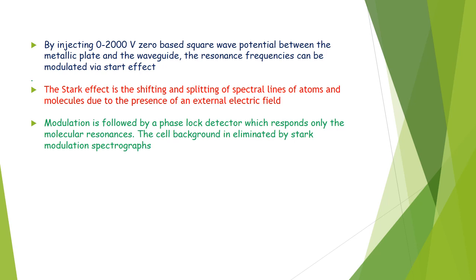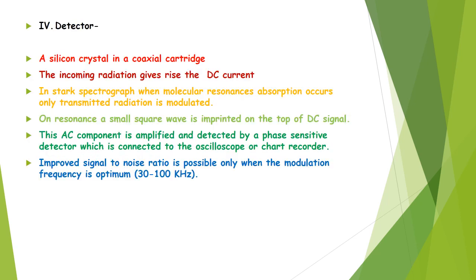Here, the resonance comes between the gas kept in the sample cell and the radiation from the klystron source in the atmosphere of the electric field of its potential 0 to 2000 volts. The cell background is eliminated by Stark modulation spectrograph.